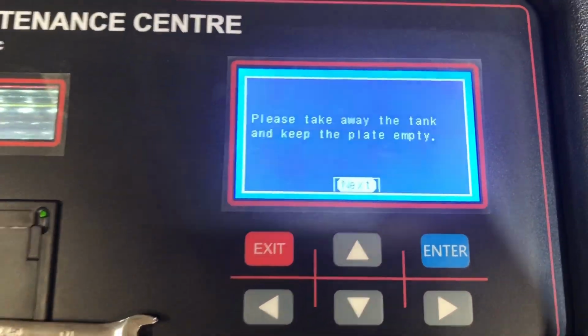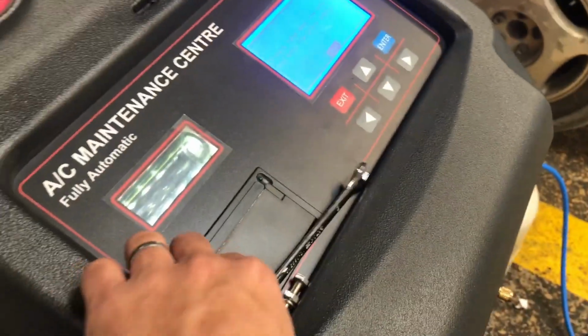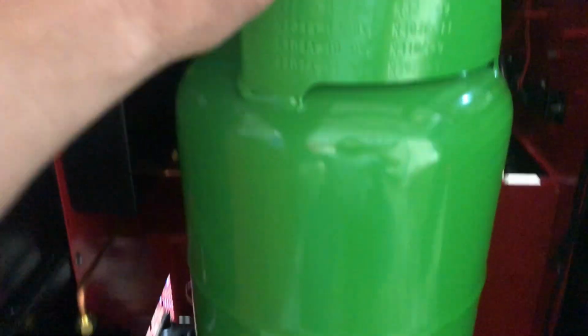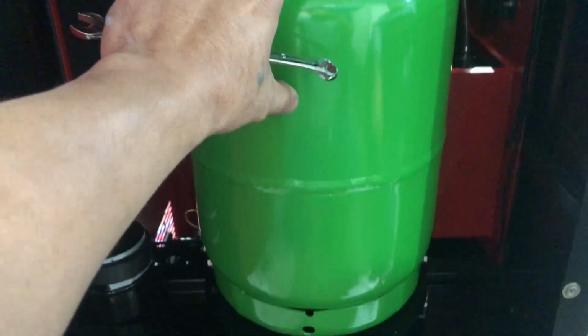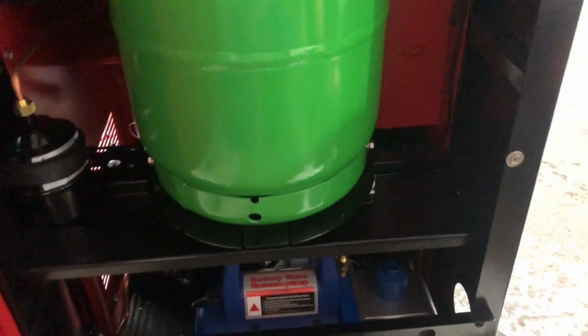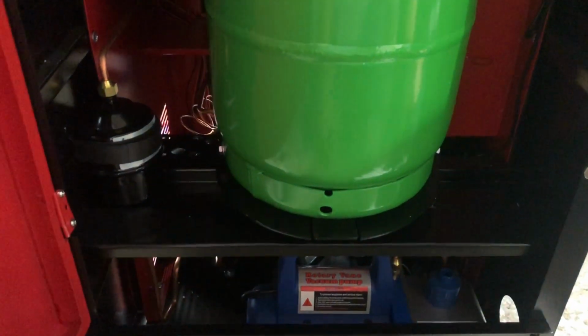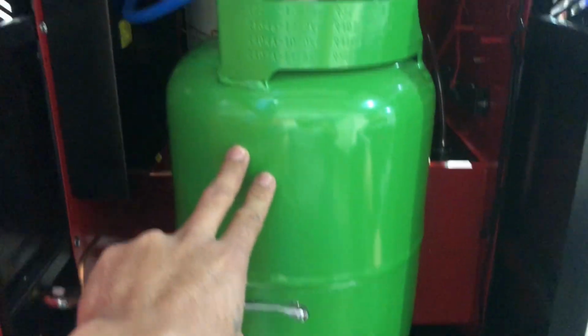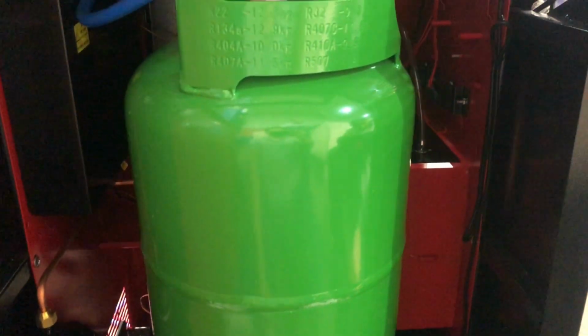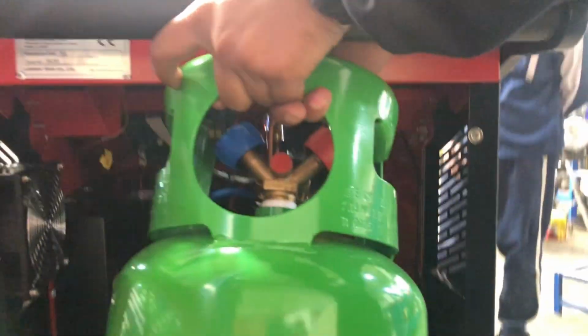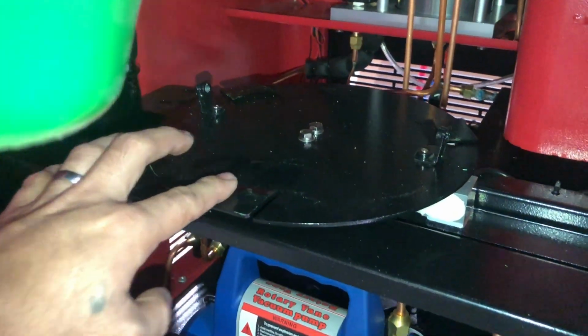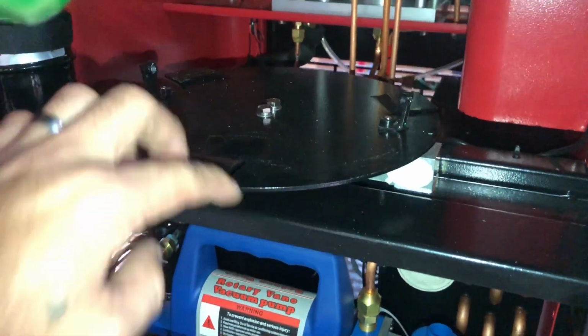Please take away the tank and keep the plate empty. Okay. The system said, just take away the tank. This is the main tank. The system said you need to remove this tank before calibration. You need to remove this tank like this, because you need to empty this plate to calibrate the scale.